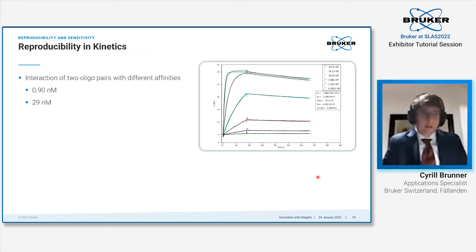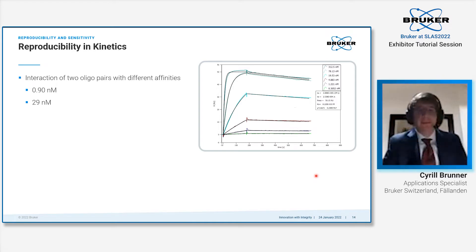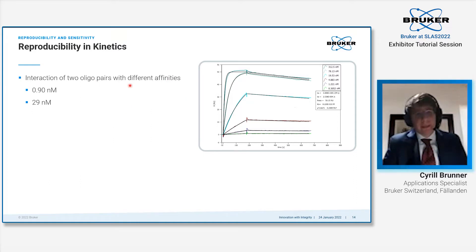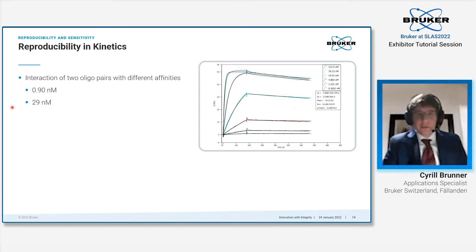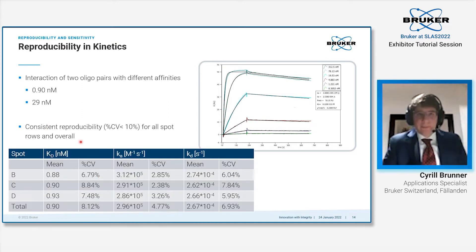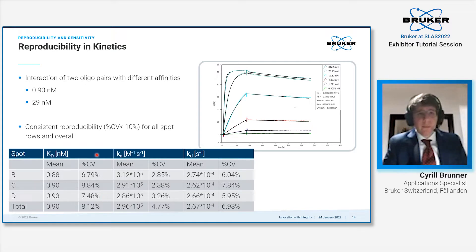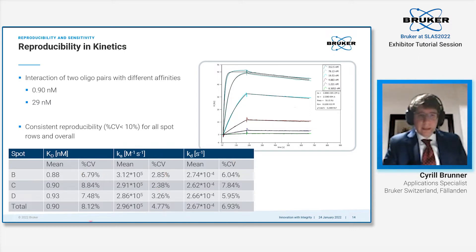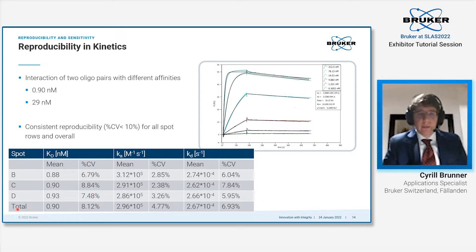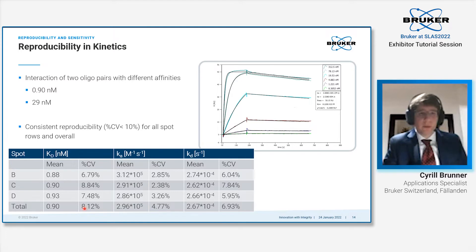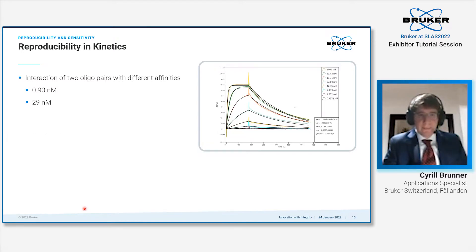Besides immobilization, the reproducibility in a kinetic assay is obviously the most important aspect for SPR. We looked at that with two oligo pairs interacting with each other. The first one has an affinity of approximately 900 picomolar, the second one in the range of 30 nanomolar. We start with the more affine one. You see here an example sensorgram—we are below 10% CV for all kinetic parameters: Ka, Kd, as well as the affinity KD, both on every sensor spot row as well as on the total, overall 24 sensor spots.